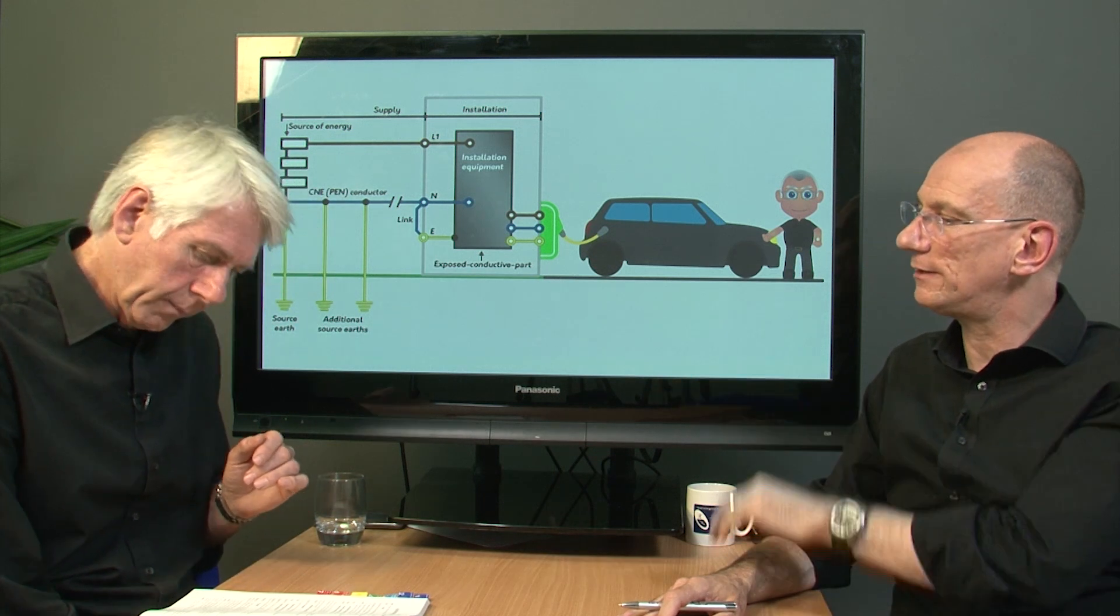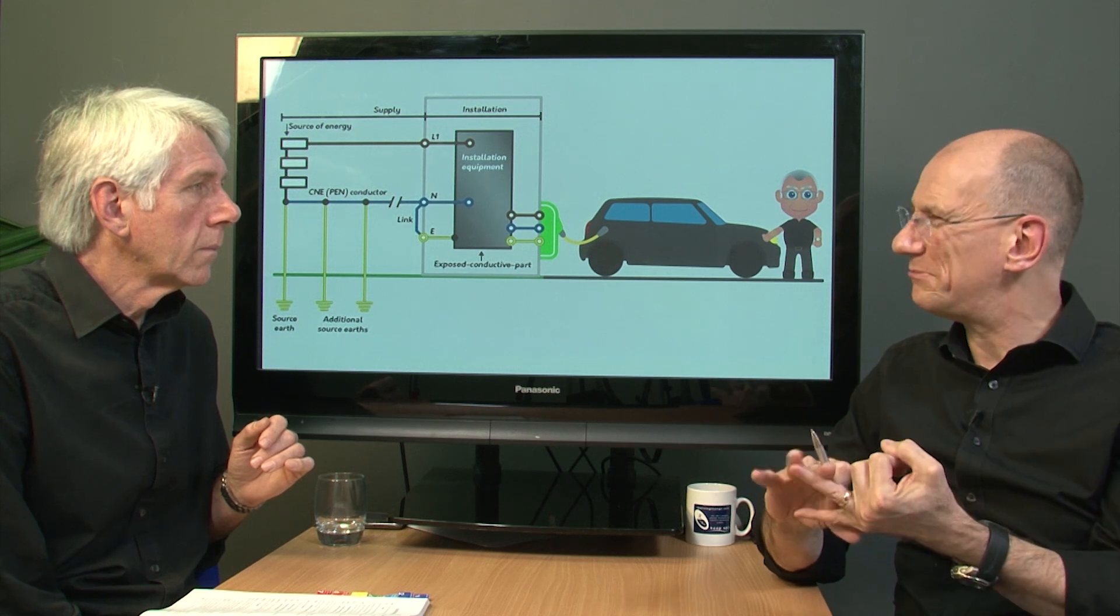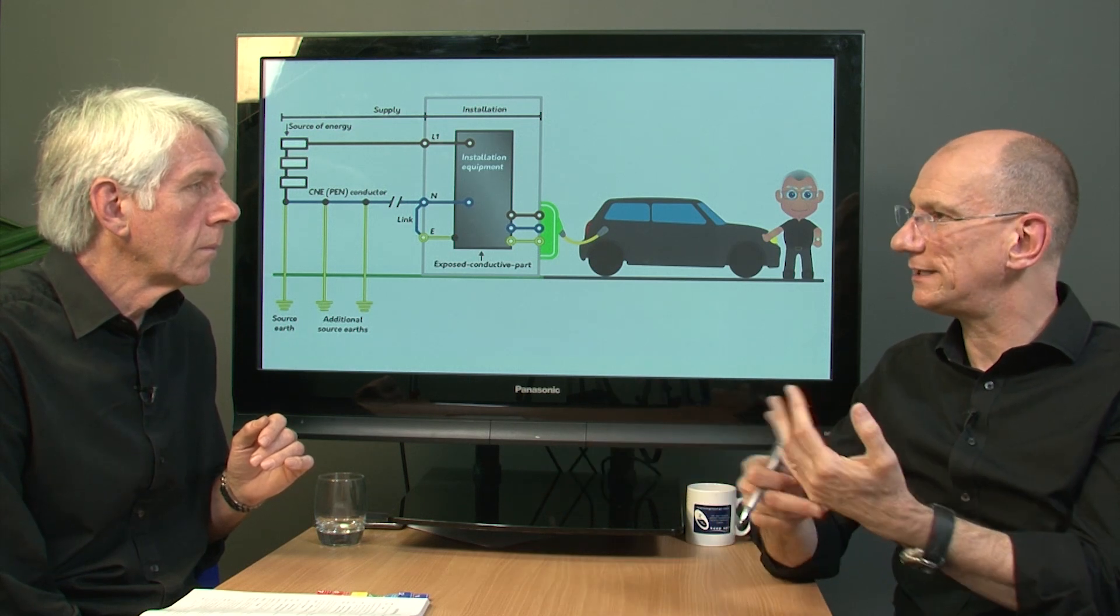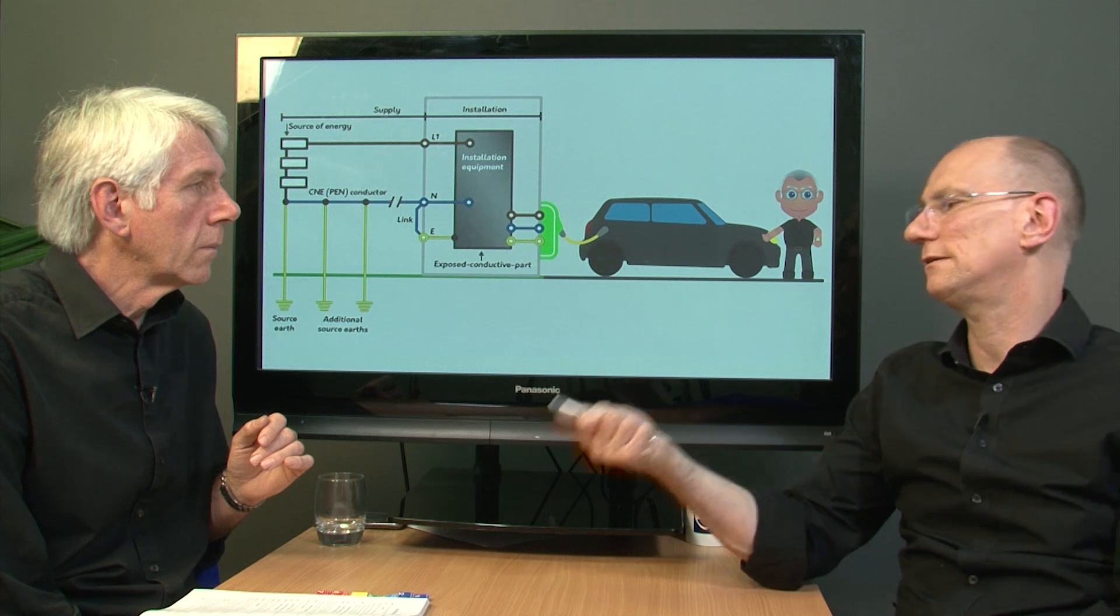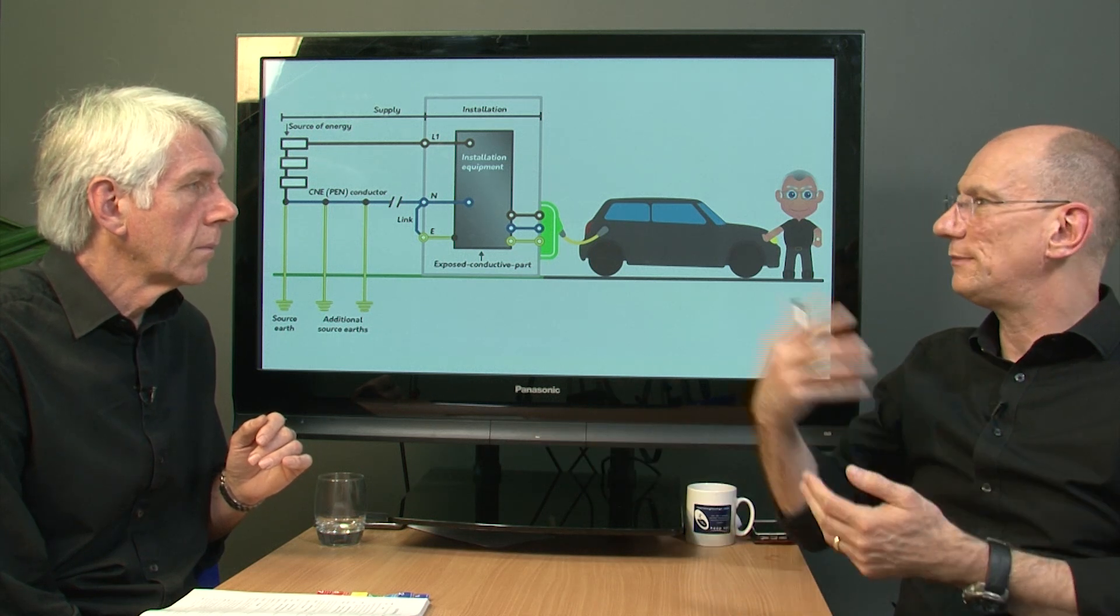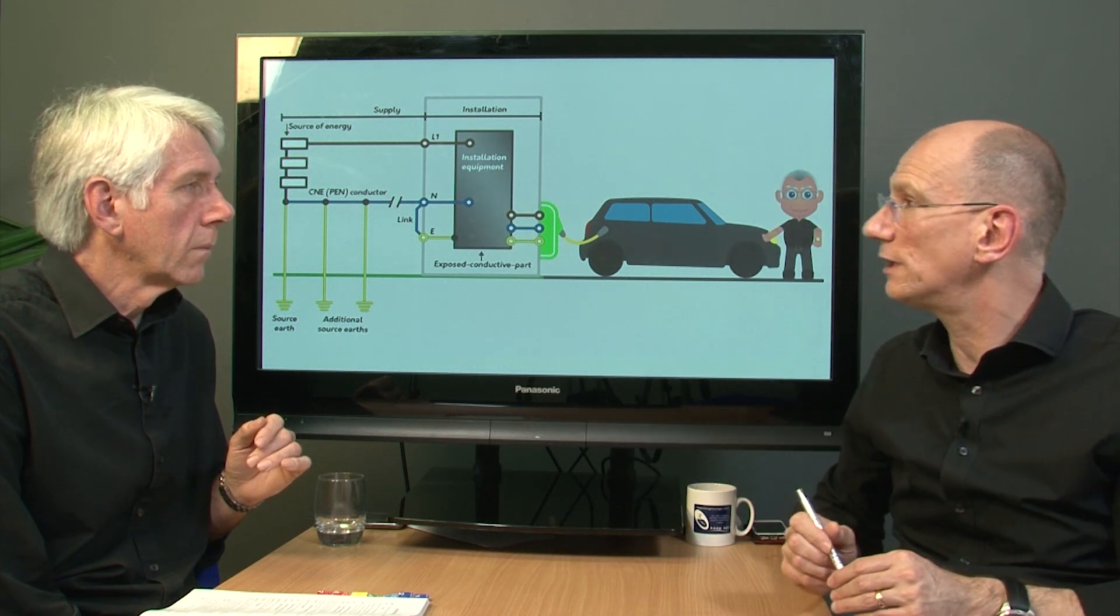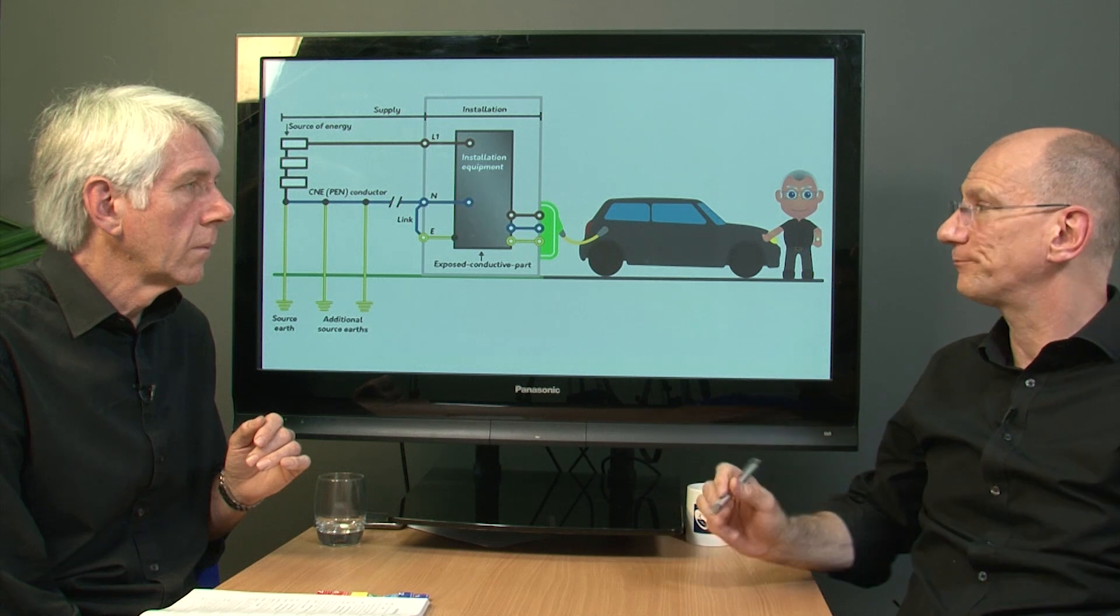And even if you are in a commercial environment, you'd want to monitor the line currents for a period of time. I mean, it's not specified there, but it certainly wouldn't be a clamp meter and take three readings in a half-hour period. Because time, loading, shift patterns and all that will have a massive impact on how the whole thing works over a period of months, if not a year.